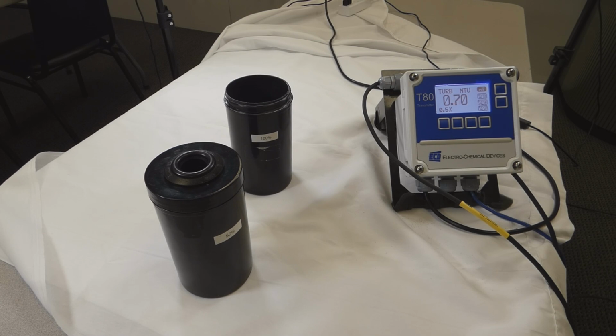If you don't have DI water, you can place the sensor facing a non-reflective surface and use that as your electronic zero. You want to wait about 2 to 3 minutes in between each calibration. This will allow the sensor to stabilize.